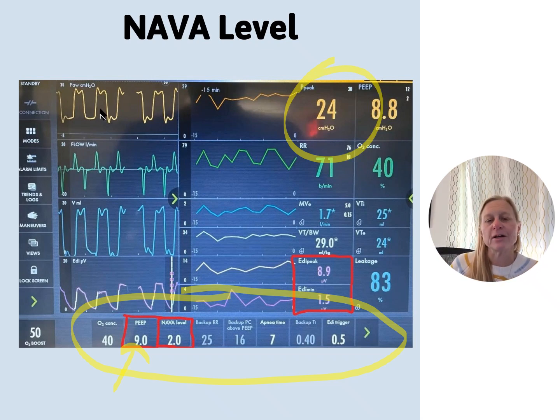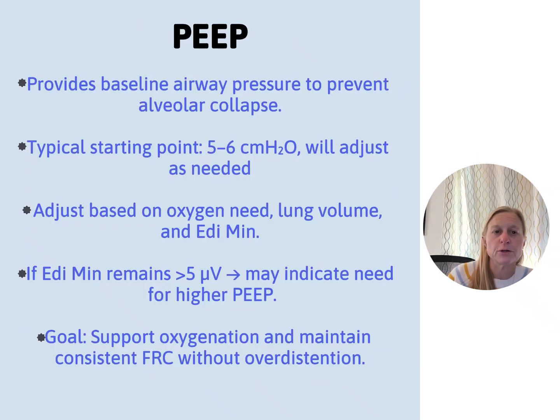That's what you got up here. So that's a calculated value. It's not even measured, it's calculated. So keep that in mind as you go along here and kind of what you're looking at. Because if your PEEP's changing around, it probably means your Edi peaks and mins are changing around, because your NAVA level is set and your PEEP is set. So important to know that as we go through. We all know what PEEP is, right? Positive end expiratory pressure. We know how it works.